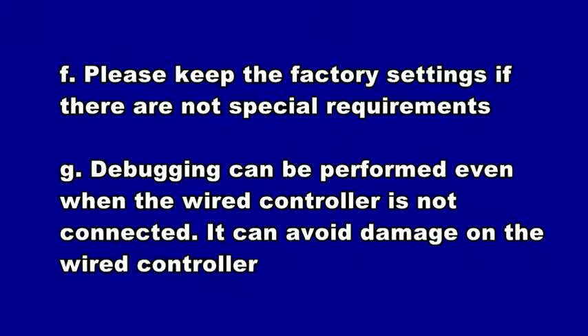D. An outdoor unit must be set as master module and only one master module can be set during debugging. E. An indoor unit must be set as master indoor unit and only one can be set during debugging. F. Please keep the factory settings if there are no special requirements. G. Debugging can be performed even when the wired controller is not connected. It can avoid damage on the wired controller.